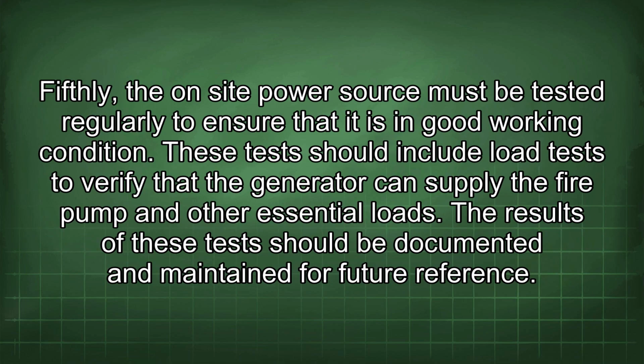Fifthly, the on-site power source must be tested regularly to ensure that it is in good working condition. These tests should include load tests to verify that the generator can supply the fire pump and other essential loads. The results of these tests should be documented and maintained for future reference.